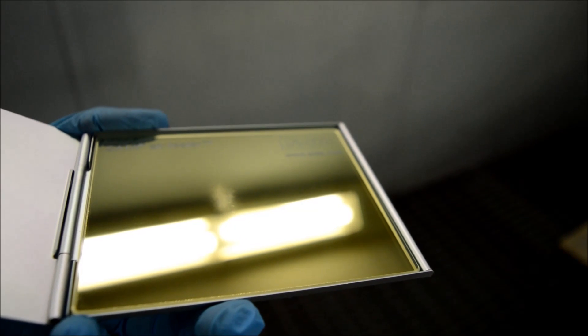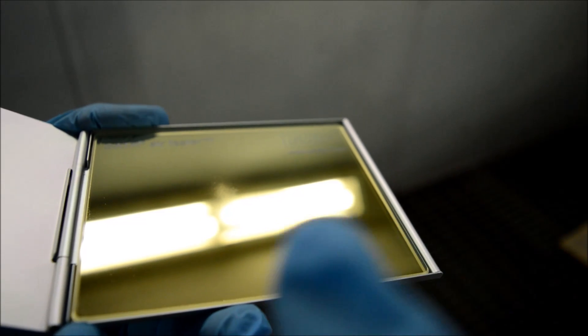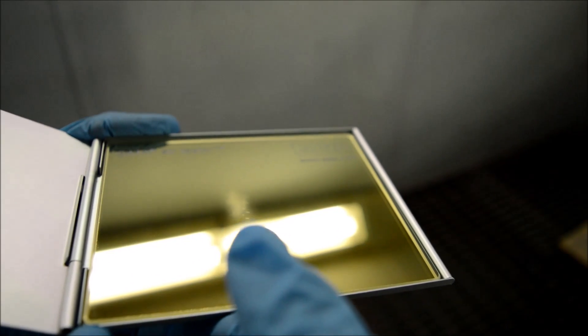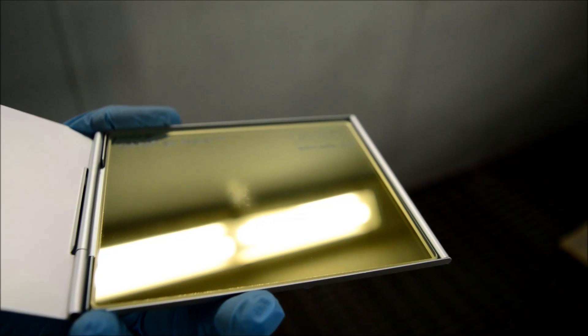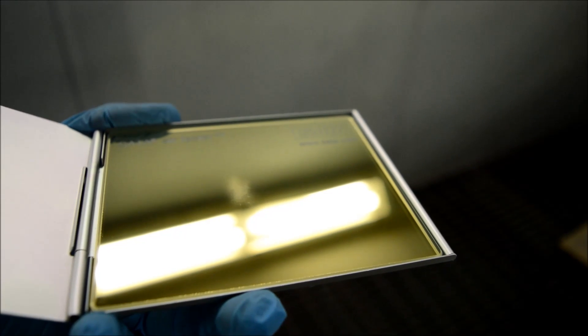We're holding this air tester up to the light now and you can see a faint haze in the middle, just around here. This shows the air test has picked up some form of contamination running through our airlines.